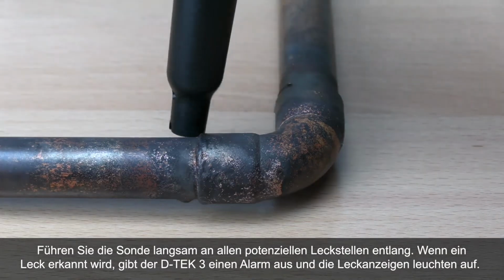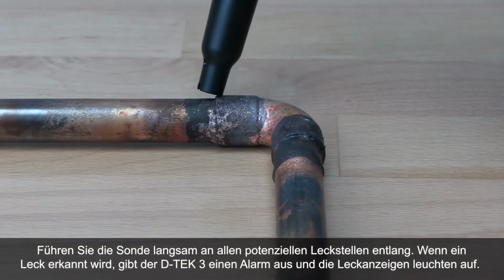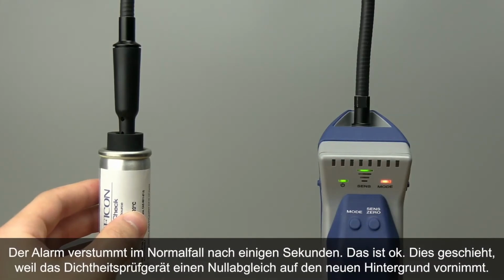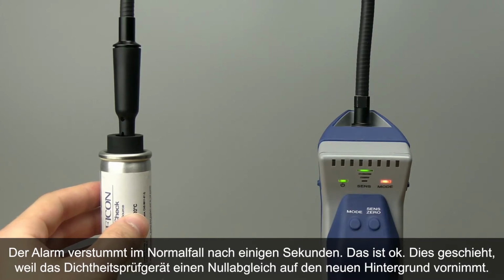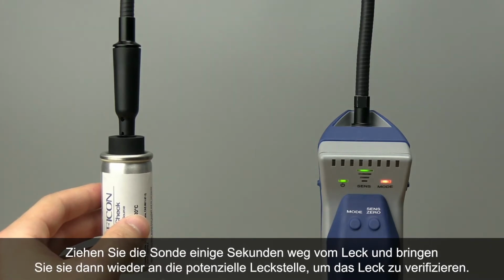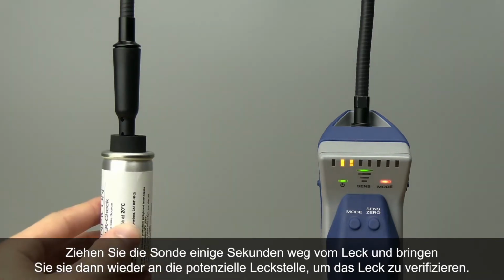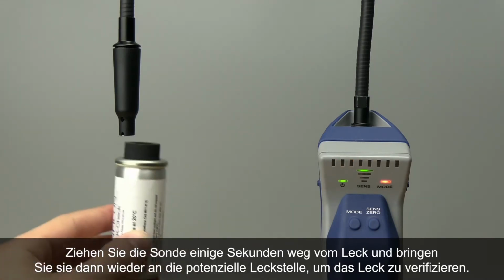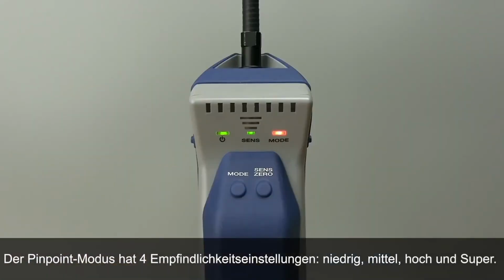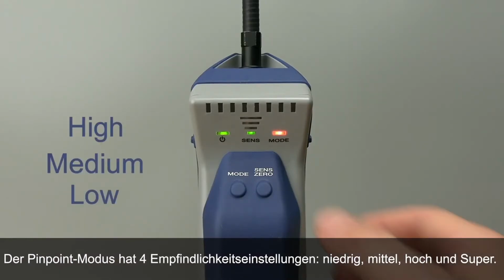If a leak is detected, D-TEK-3 will alarm, and the leak indicators will illuminate. The alarm will likely stop after a couple seconds. That's okay. It's the leak detector zeroing to the new background. Pull the probe away from the leak for a few seconds and return it to the suspected leak site to verify the leak. Pinpoint mode has 4 sensitivity settings: low, medium, high, and super.